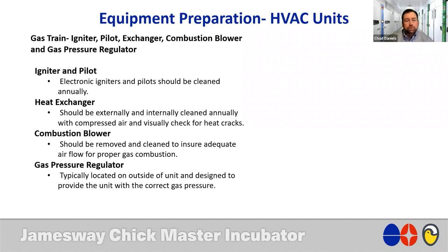And in both cases, the unit itself is designed to only operate at a specific pressure. So it'll have a gas pressure regulator that by design has to be set to a specific pressure. And it's good as you near the extreme winter conditions or cold time of the year, it's a great idea to make sure that you check that gas pressure again to make sure that you have a unit that's operating at its designed heating capacity. Because if the pressure's wrong, it won't function correctly.